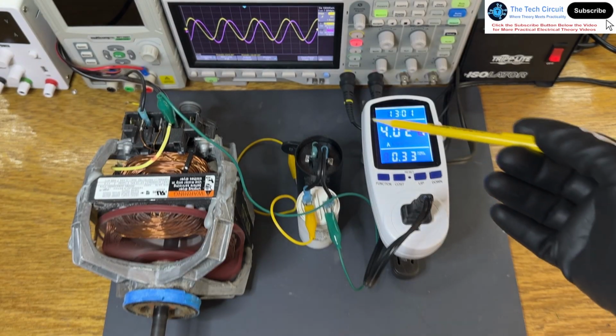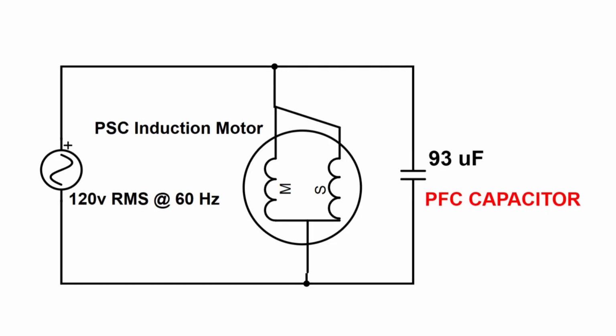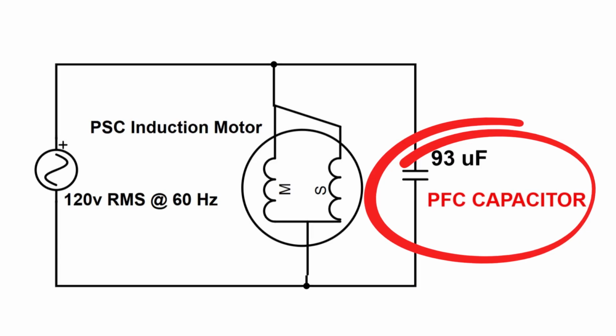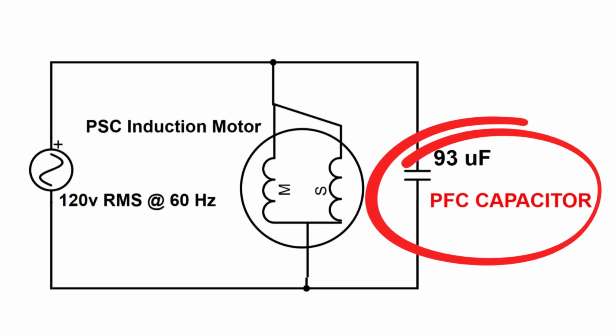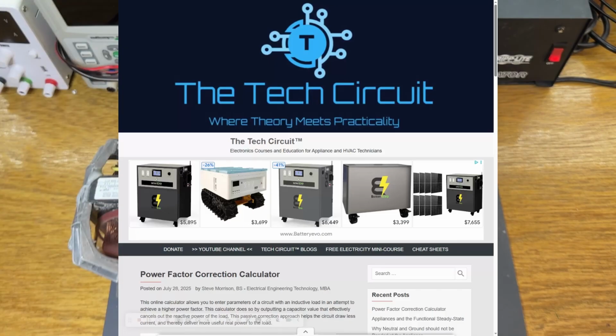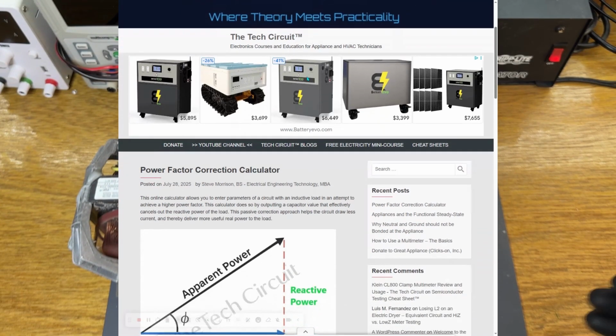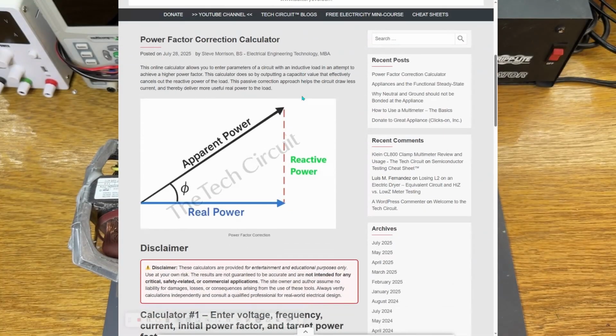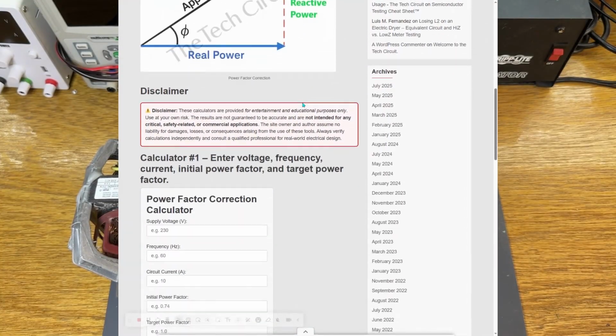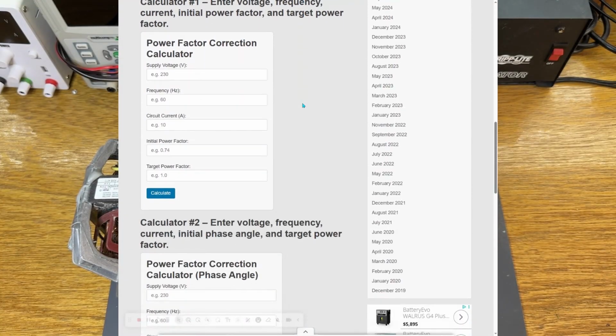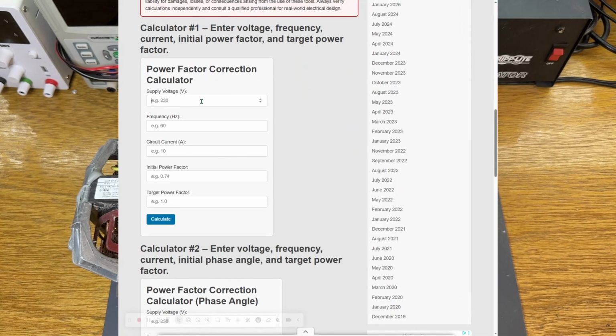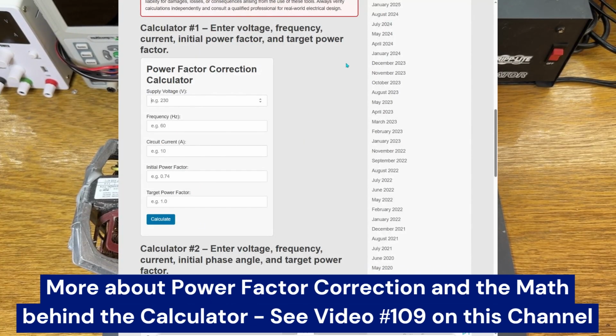We'll do that by calculating the value of a capacitor to place in parallel with the motor. This capacitor cancels out most of the unused reactive current. To determine the correct capacitor value, I'll use a power factor correction calculator that I developed, which uses trigonometry and algebra under the hood. You can find this calculator at techcircuit.org, linked below in the description. If you want a deeper dive into power factor correction and the math behind the calculator, check out video 109 on this channel, also linked in the description.